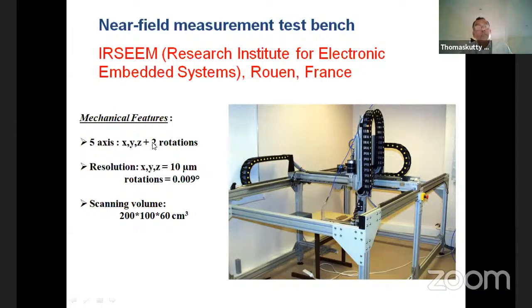They have the setup, whose mechanical features are 5 axes: X, Y, Z plus 2 rotations. The resolution of X, Y, Z is 10 micrometer, and the rotations have 0.009 degree resolution. The scanning volume is 200 by 100 by 60 centimeter cube. So this is an instrument which is needed. Without it you cannot do EMC tests and other things at IC level or on very small devices, microwave devices.